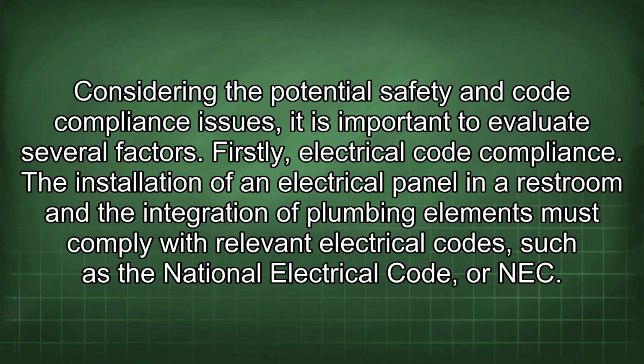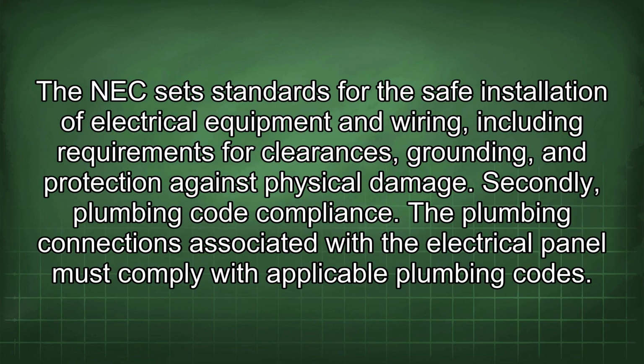Considering the potential safety and code compliance issues, it is important to evaluate several factors. Firstly, electrical code compliance. The installation of an electrical panel in a restroom and the integration of plumbing elements must comply with relevant electrical codes, such as the National Electrical Code, or NEC. The NEC sets standards for the safe installation of electrical equipment and wiring, including requirements for clearances, grounding, and protection against physical damage. Secondly, plumbing code compliance.